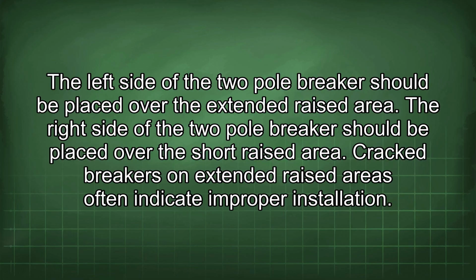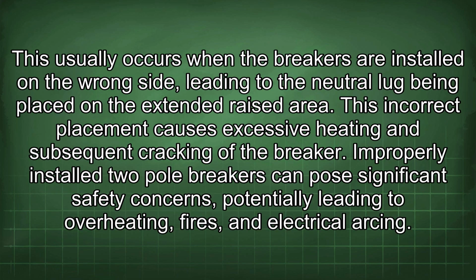Cracked breakers on extended raised areas often indicate improper installation. This usually occurs when the breakers are installed on the wrong side, leading to the neutral lug being placed in the extended raised area. This incorrect placement causes excessive heating and subsequent cracking of the breaker.